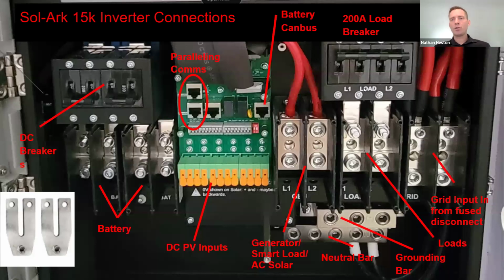On the right side of your screen, you have the AC connections in the inverter. Starting at the bottom, there's a neutral bar down here at the very bottom to connect all your neutrals. Your neutral ground bar should be inside your service disconnect. So that's that 200 amp fuse disconnect where you first come out of your meter. And then you have a separate grounding bar here for the inverter. You have the generator and smart load connection on the left side of the screen here. And then your loads output is here. It's fed with a 200 amp breaker. You'd feed your main loads panel out of this connection. On the right side of your screen, this is coming in from that fused service disconnect.